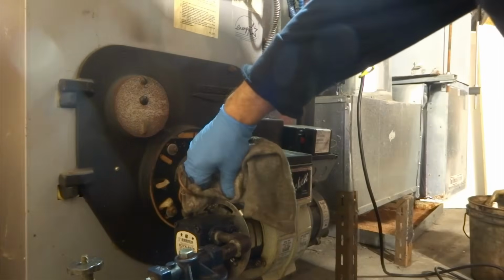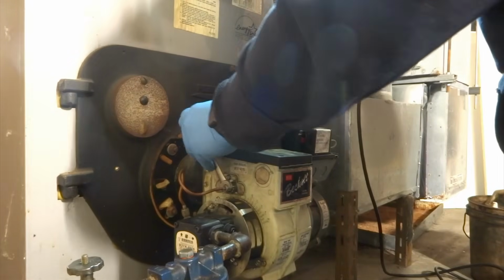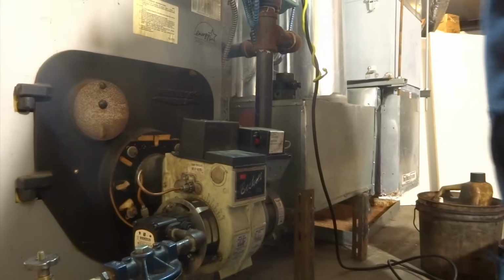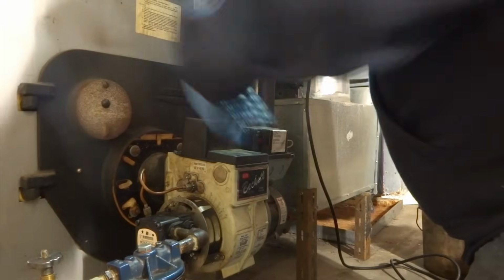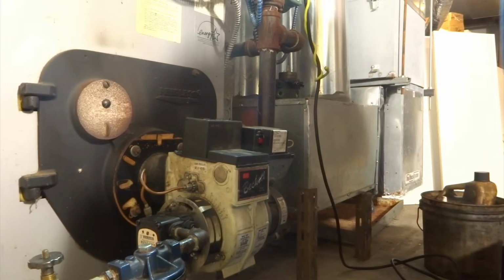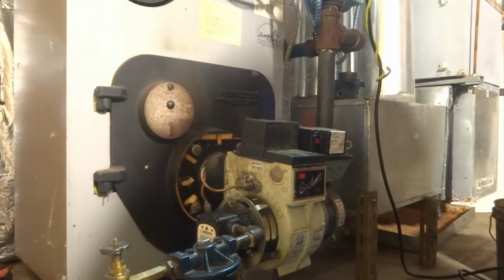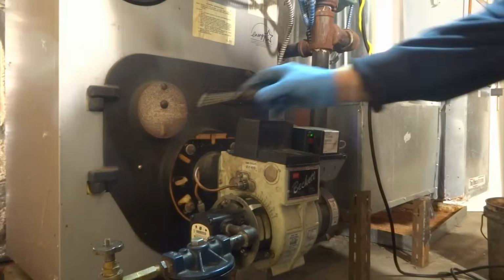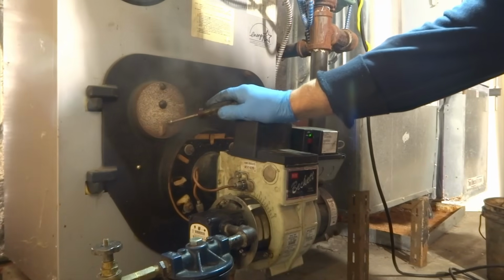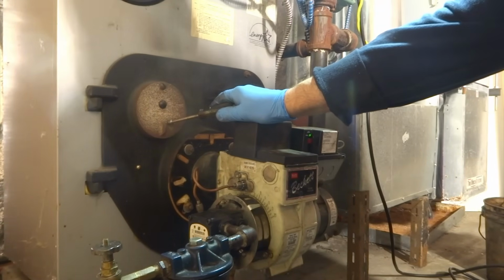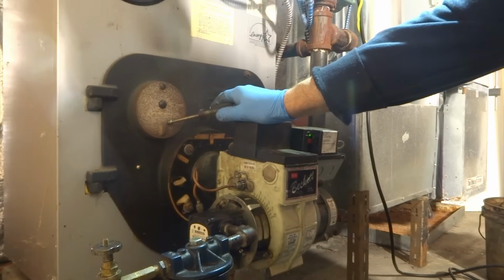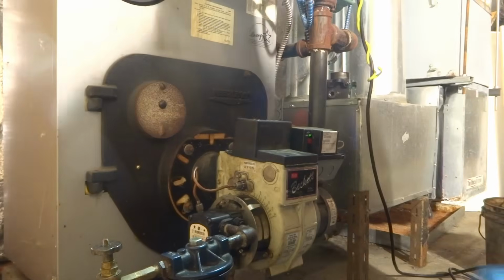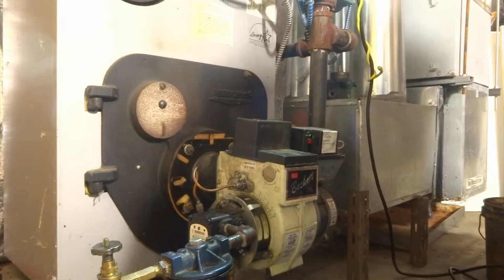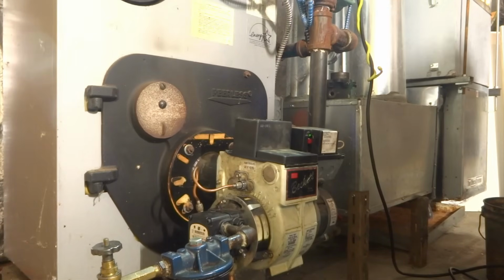When I start this up, if it starts smoking, you got to keep it running, because if not, it could explode. We'll fire it up, and if it's smoking, you got to keep it running. Might be oil in there. Get the smoke, keep it running. That smoke will go up the chimney. You don't want to shut it off because it can explode. You gotta keep it running. That's why I always tell people not to keep it in these somewhere. Do people listen? No, they don't.